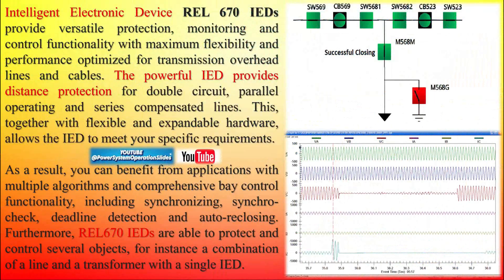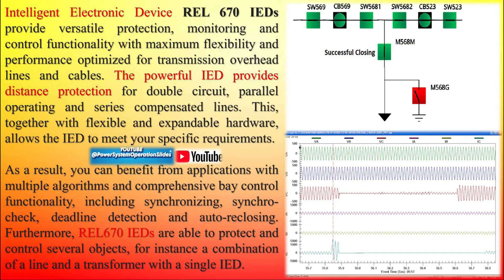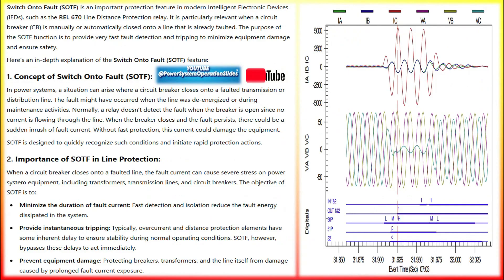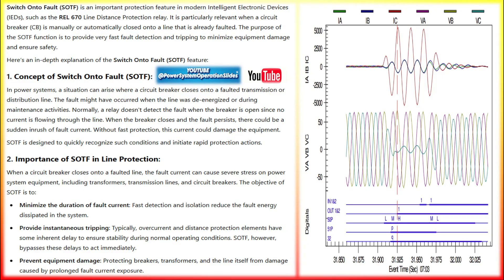Switch-on-to-fault (SOTF) is an important protection feature in modern intelligent electronic devices (IEDs) such as the REL670 line distance protection relay. It is particularly relevant when a circuit breaker (CB) is manually or automatically closed onto a line that is already faulted. The purpose of the SOTF function is to provide very fast fault detection and tripping to minimize equipment damage and ensure safety.